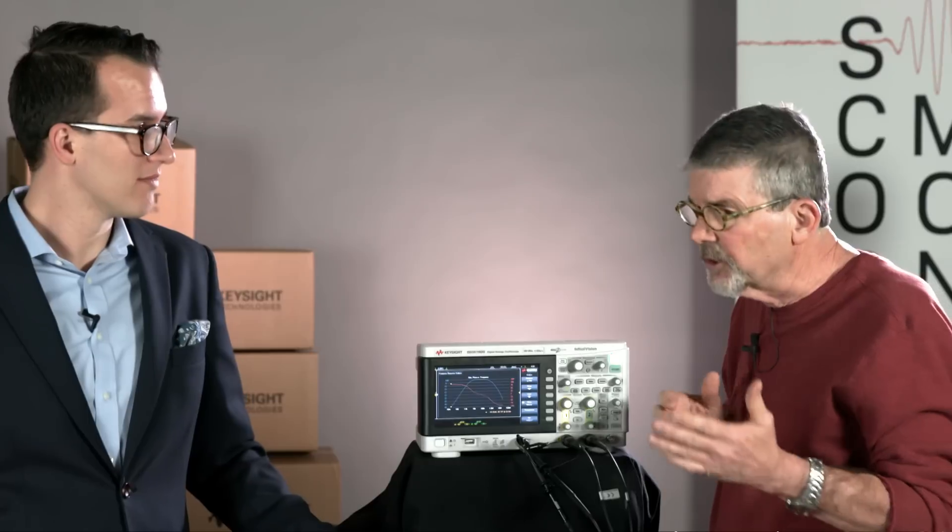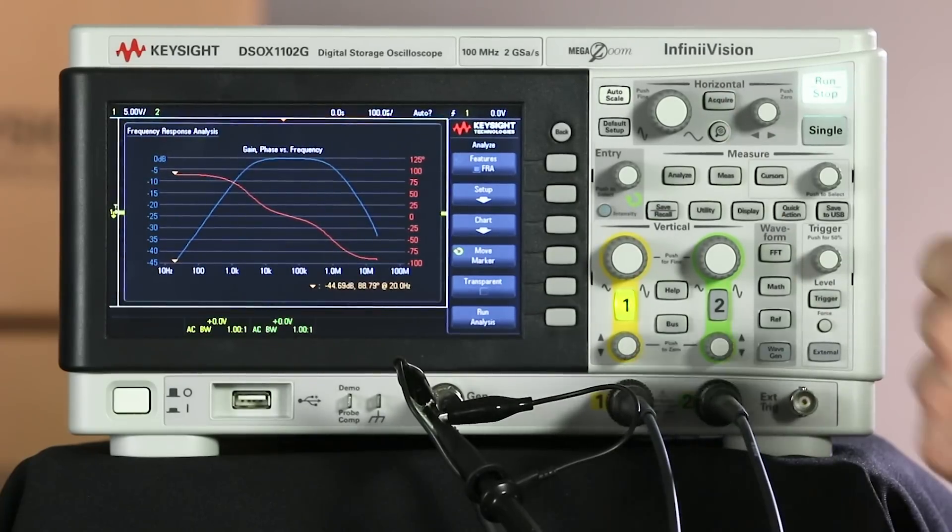And it'll change based on the settings that you have for the minimum and maximum frequencies. The test time will change. That's correct. Yeah, if you start at higher frequencies, it's going to run a lot faster. So naturally, you would just test the frequencies that you care about, not necessarily run the whole spread. So here we see the final plot.